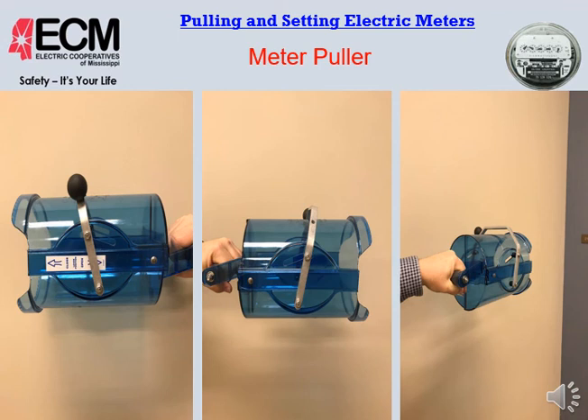The good thing about this device is that if you're pulling or setting a meter and have a fault condition - say the meter goes ballistic for some reason - most of the arc flash you'd receive is going to be contained inside the device. That does cause a lot of damage to it, and it could possibly need to be replaced afterward.